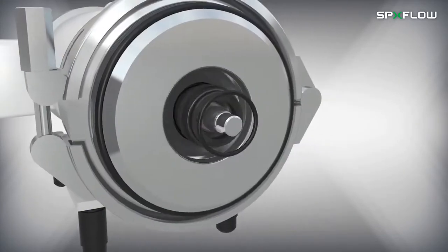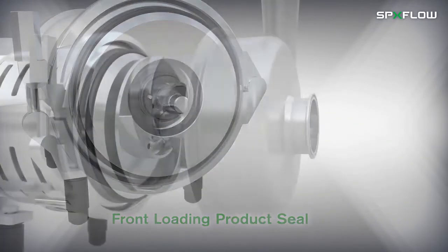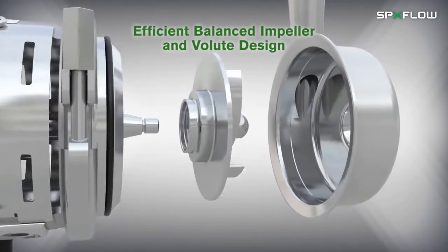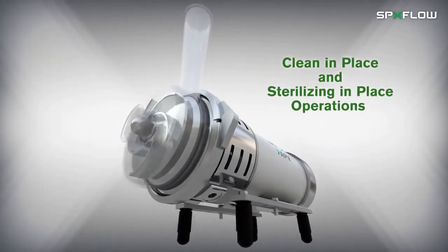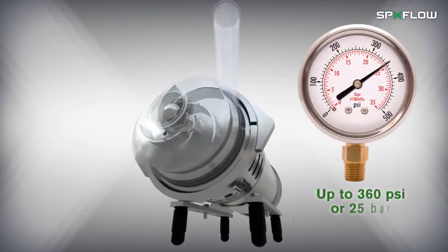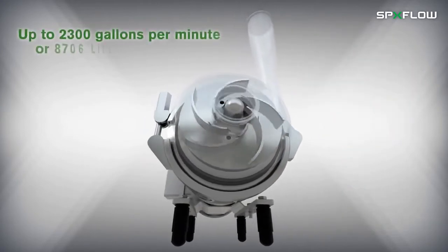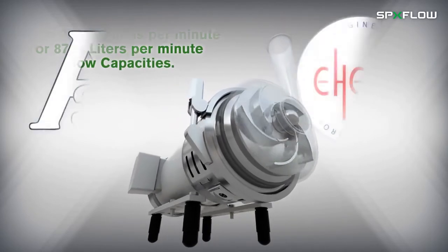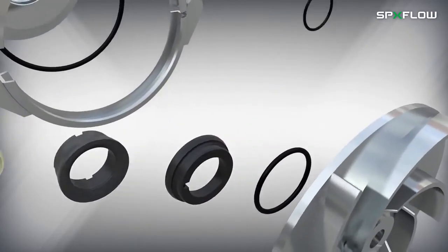front-loading product seal, efficient balanced impeller and volute design, designed for clean-in-place and sterilizing-in-place operations, up to 360 PSI or 25 bar pressure capabilities, up to 2,300 gallons per minute or 8,706 liters per minute flow capacities, 3-A and EHEDG certified, and easy and cost-effective maintenance.